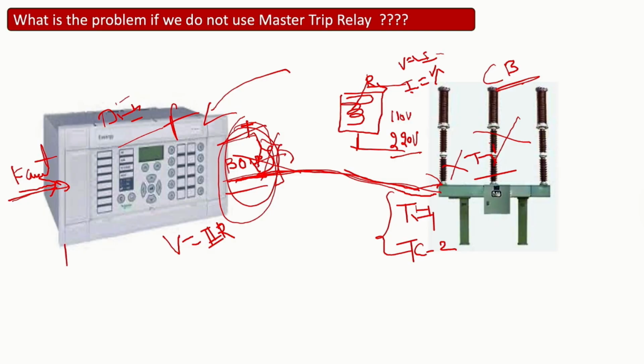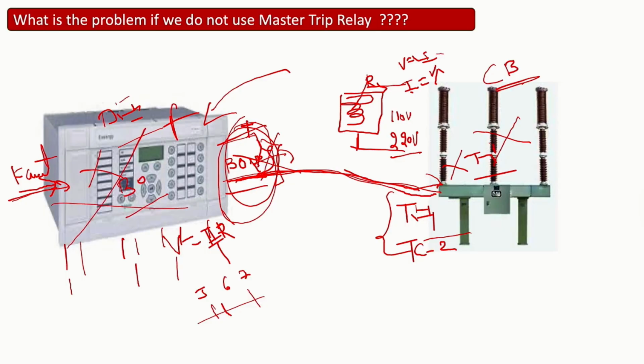Secondly, our relays have limited binary outputs, which we use for many different things. Some for alarms, some for tripping, some for signaling, some for other uses. Whatever we use, we have limited outputs. Some have 5, some have 6, some have 7. If a breaker fails, and one of our binary outputs goes out each time, ultimately, it could be that this relay has no BO at all. So, this relay is useless. No matter how expensive a relay is, without binary outputs, it's useless.